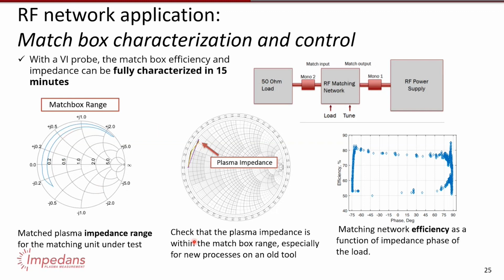One critical thing is, if you're running new processes on old tools, you can't guarantee that your matchbox is still matched to the new plasma impedance. You may measure the plasma impedance and find it's out here, beyond what this matchbox can reach. That means you'll always have reflected power, common matchbox failures, matchbox overheating, thermal runaway effects, and so on.